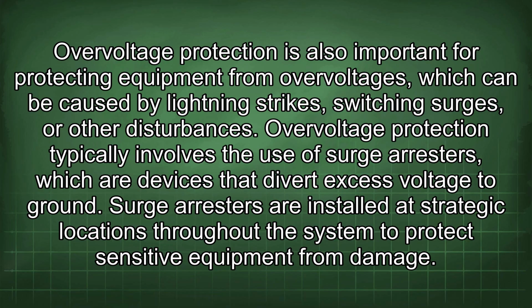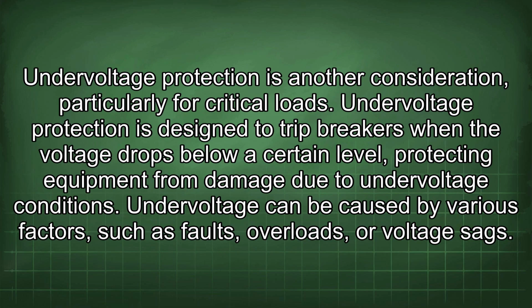Overvoltage protection is also important for protecting equipment from overvoltages, which can be caused by lightning strikes, switching surges, or other disturbances. Overvoltage protection typically involves the use of surge arresters, which are devices that divert excess voltage to ground. Surge arresters are installed at strategic locations throughout the system to protect sensitive equipment from damage. Undervoltage protection is another consideration, particularly for critical loads. Undervoltage protection is designed to trip breakers when the voltage drops below a certain level, protecting equipment from damage due to undervoltage conditions. Undervoltage can be caused by various factors, such as faults, overloads, or voltage sags.